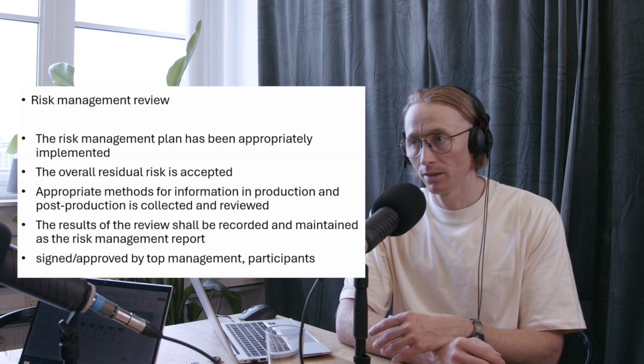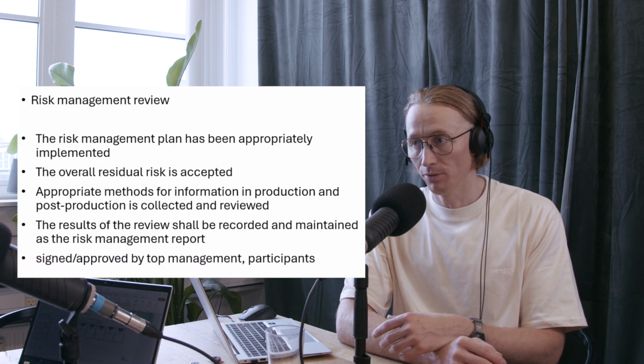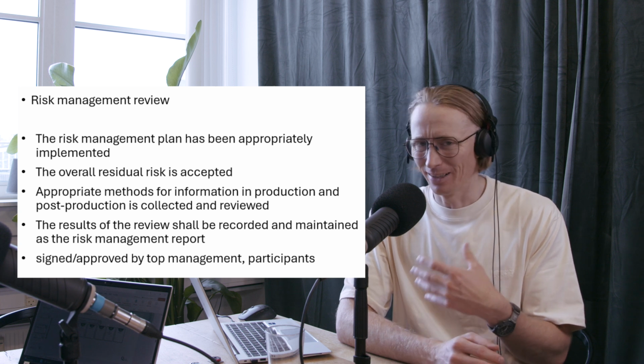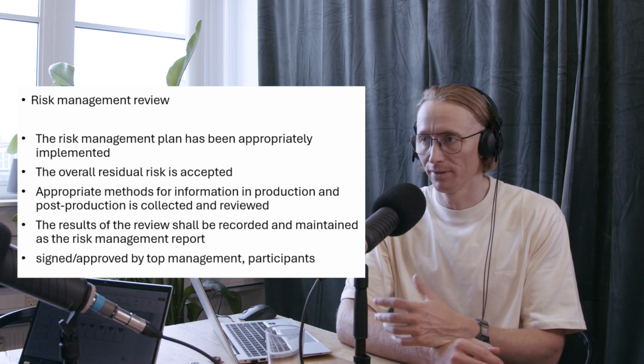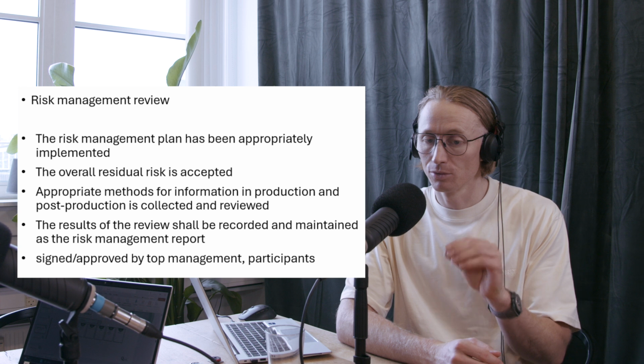And then from there, you need to go through your plan. Is your plan okay? Go through your analysis. And then from your analysis, you create a new report. And then the last document that you also need, which is very important, is your risk management review. So top management need to review, or depending on how your structure in the company is, you have set a certain group that needs to do a management review of your risk management. And that's very important because if you miss it, you don't follow the standard. Exactly.